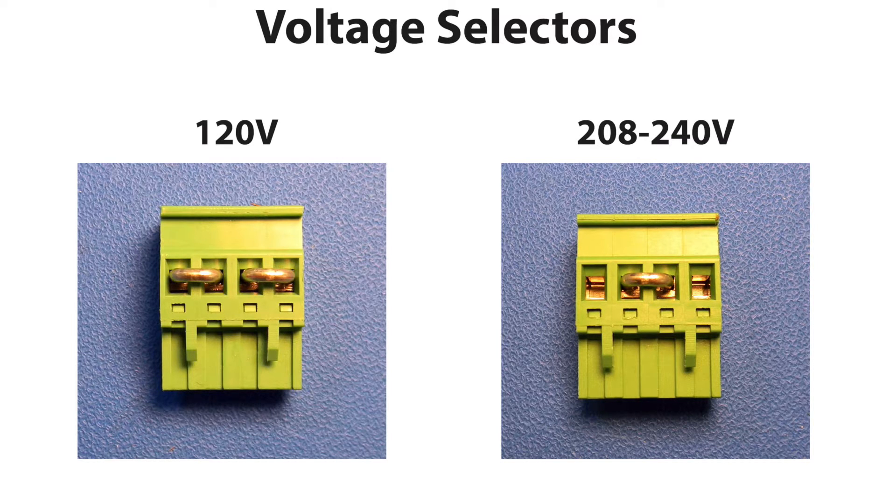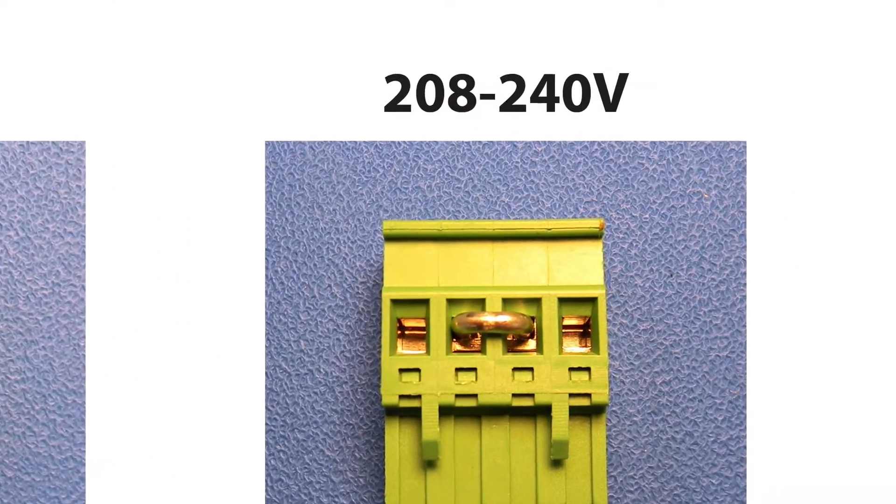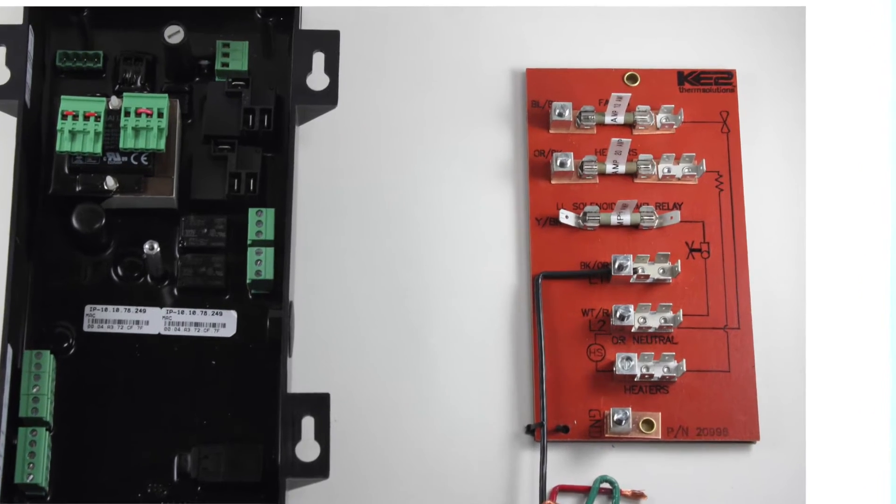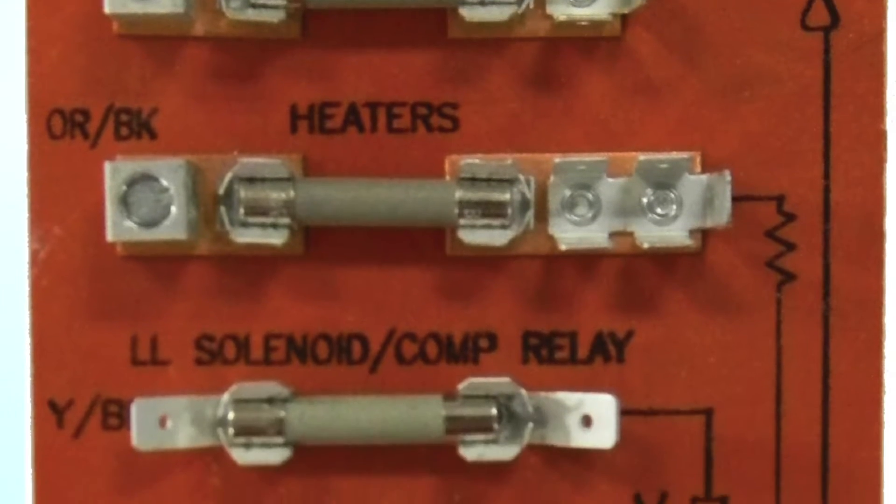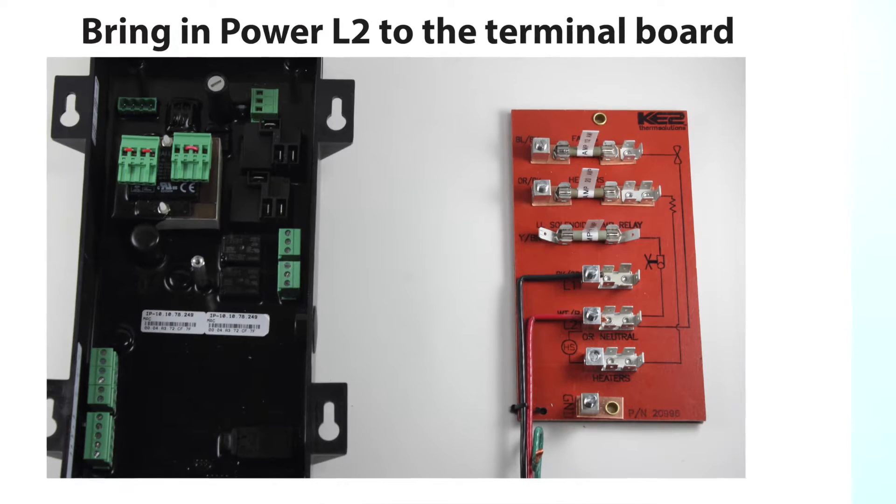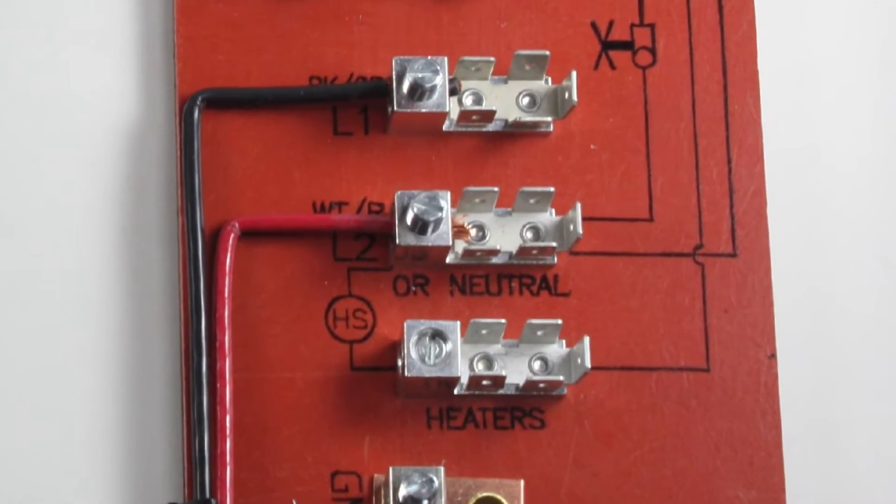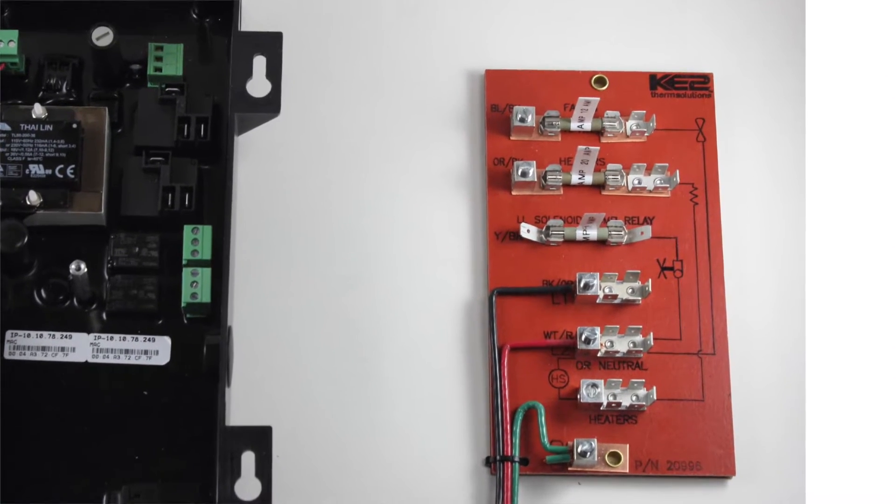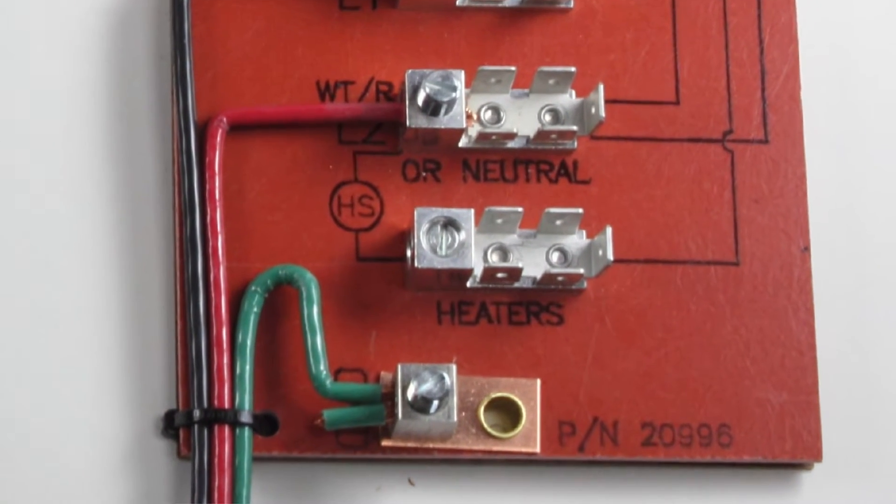Just select the correct green pluggable connector for your application. This example uses 208 volts as the uninterrupted power source. Place black L1 in the L1 location as shown on the terminal board. The terminal board has all of the fuses pre-installed. Place red line 2 in the L2 location as shown on the terminal board.